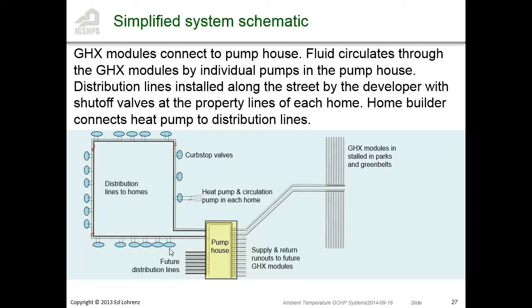It's a really simple system to install, same size pipe all the way around, half the pipe to install. One thing we can do with this system that I'm not sure you could do with a single pipe system is feed it from both ends. We can isolate this section here or that section there, we've got a valve here and here. These houses can be fed from here and the return can go back there, like a municipal water supply service.